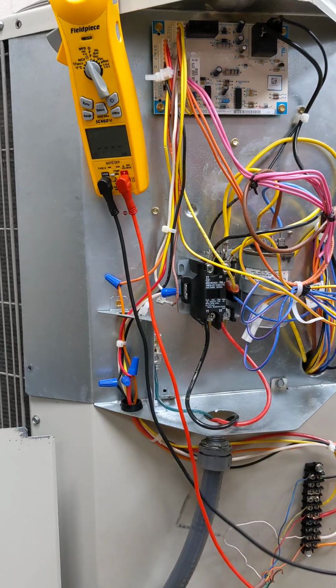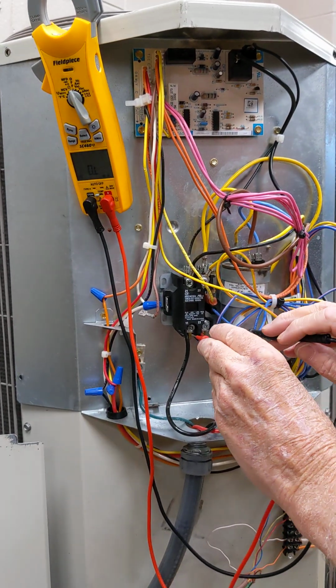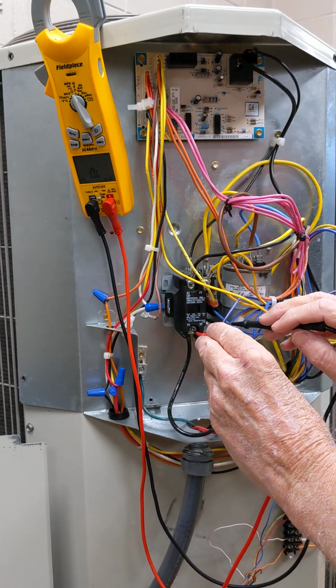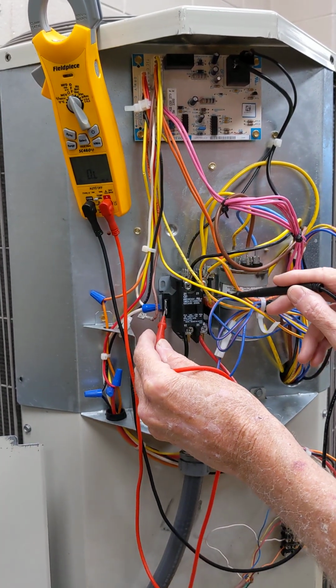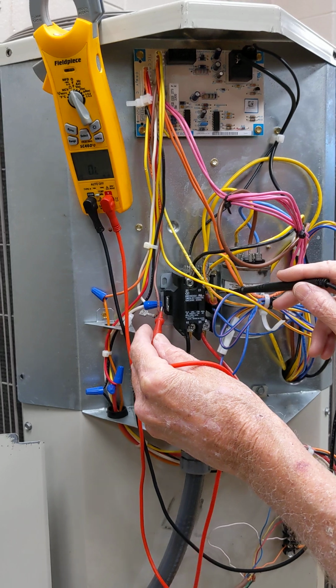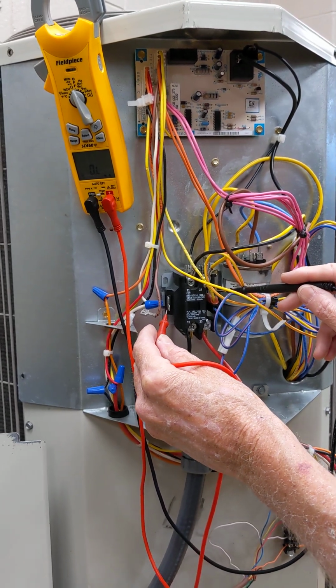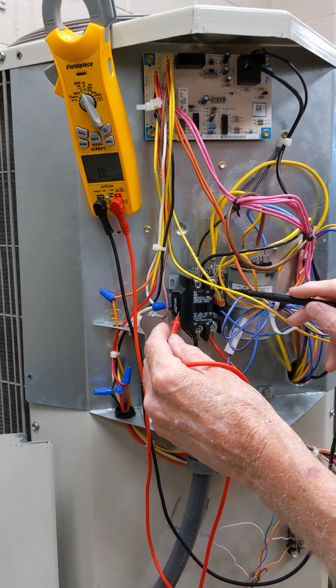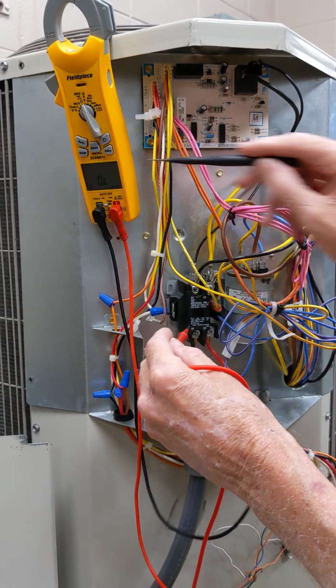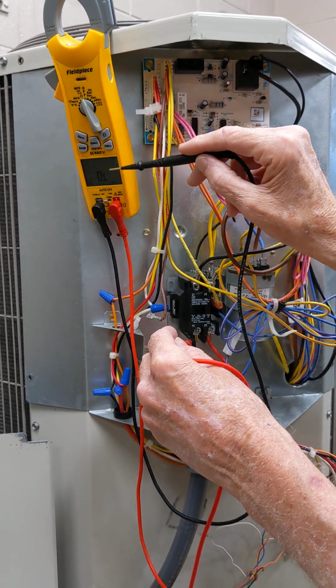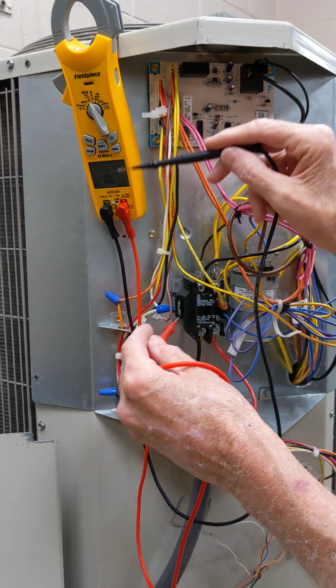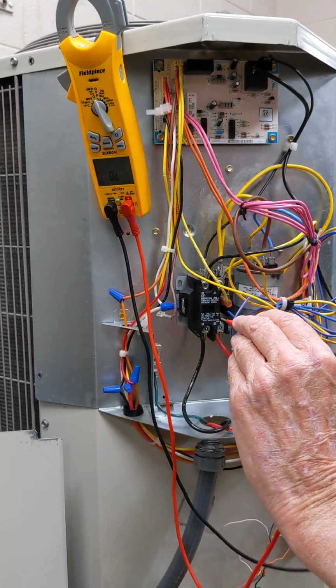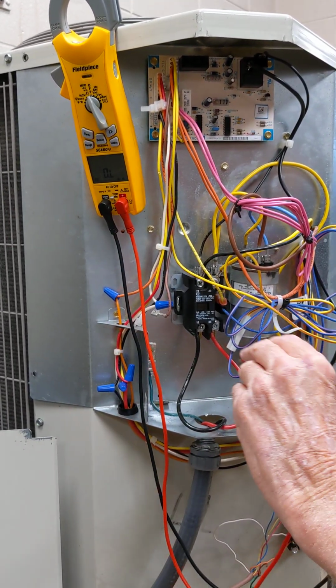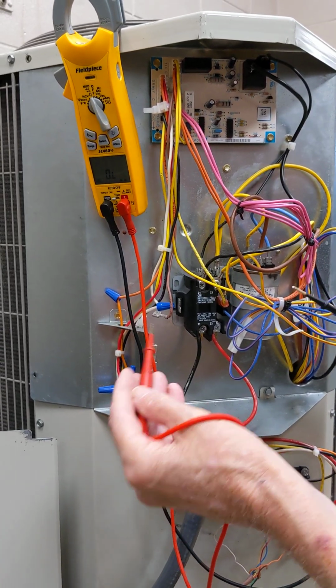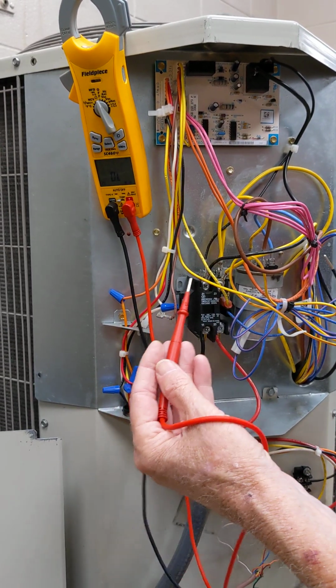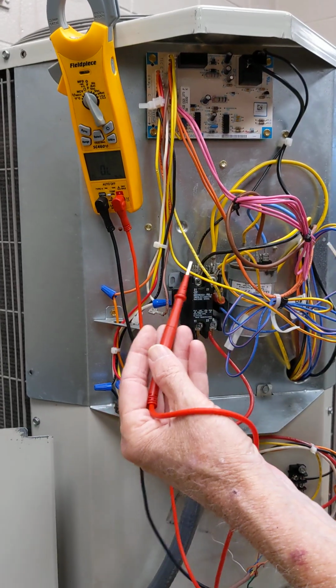So, unpowered, besides the safety part of the unpowered, I want to check the ohms across the winding, which is the coil, the contactor coil, to see if it's intact and can do work. If it's OL, the coil is bad. If it's really close to 0, 1 or 2 or something, then it's bad. And I don't even need to do the live check. But, you know, I could do the live check, but why do it? I already know it's bad. It needs to be replaced.